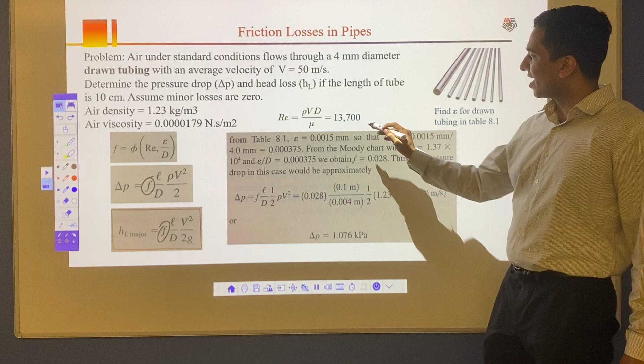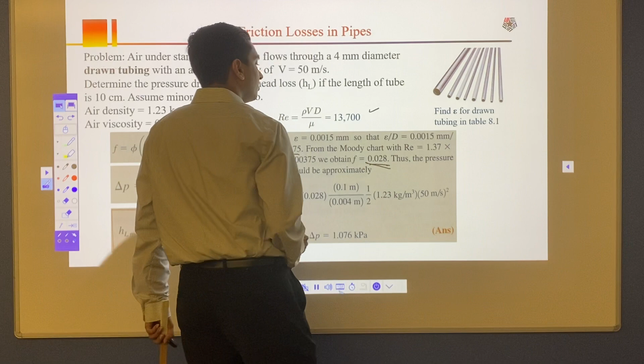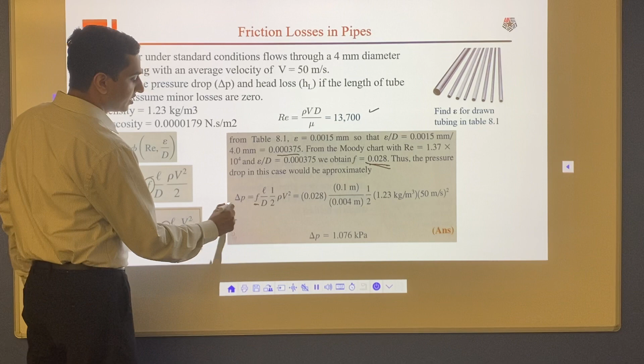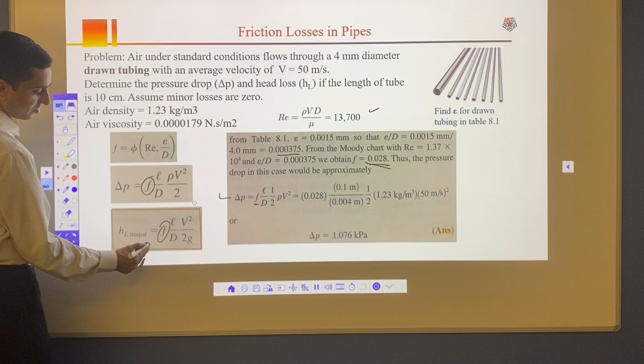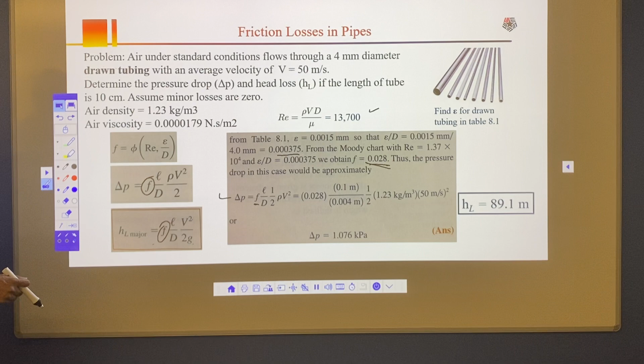So if you do your calculations, you will get epsilon by d of around 0.000375. Then you use the Moody chart, and from that you will get your friction factor as 0.028. Once you have that, you can use that friction factor here to calculate pressure drop. Then use the same friction factor here, and you should be able to calculate the major head loss, that's due to friction, which is around 89 meters. So that much head is lost because of the friction.